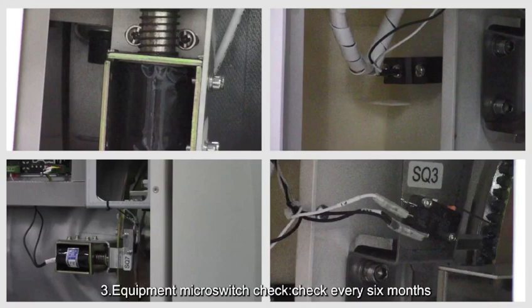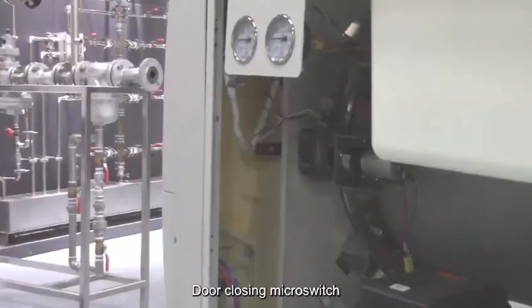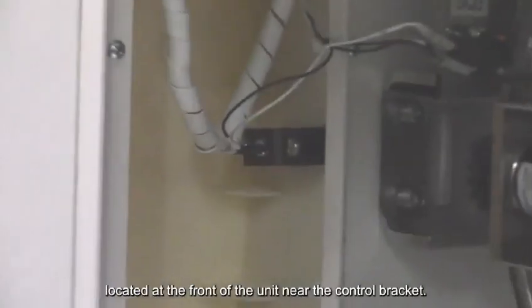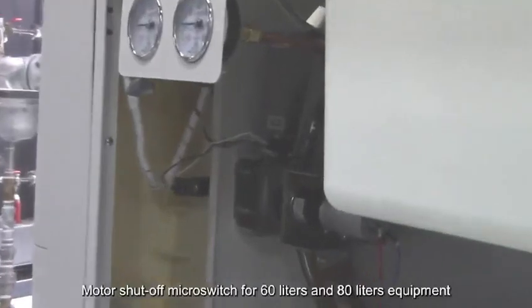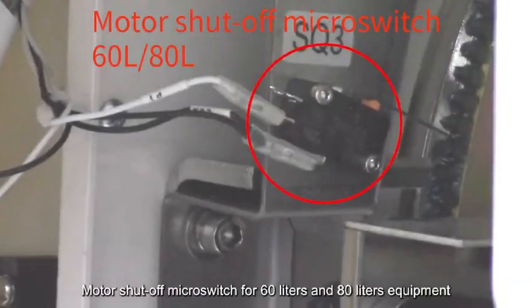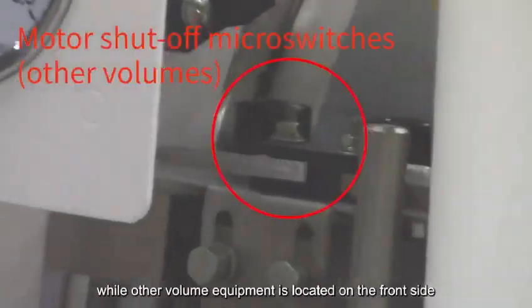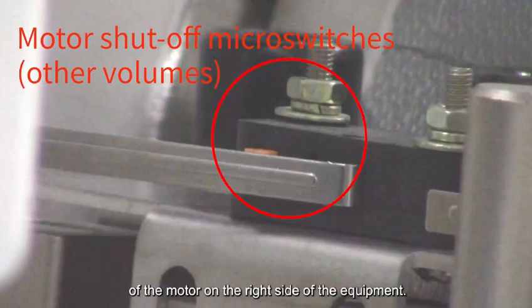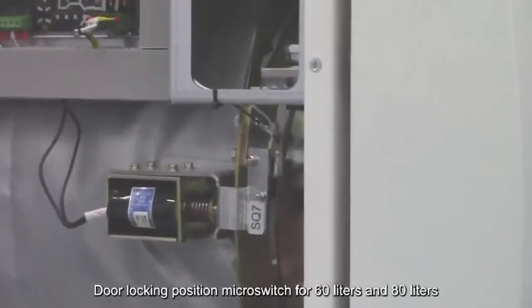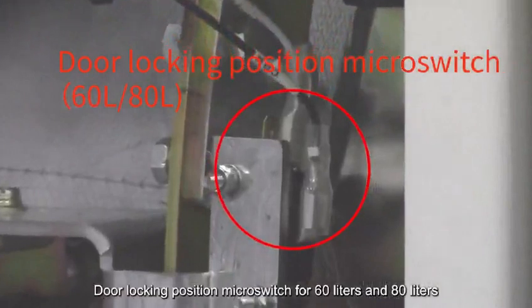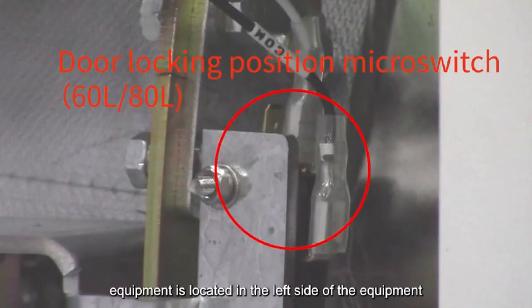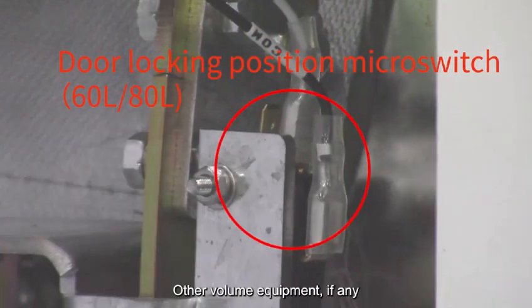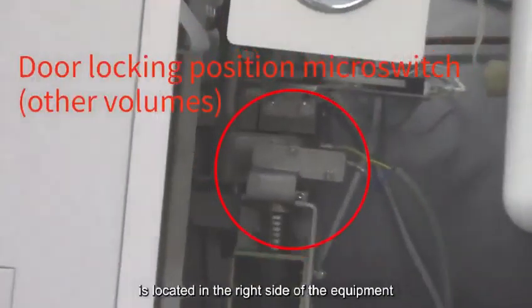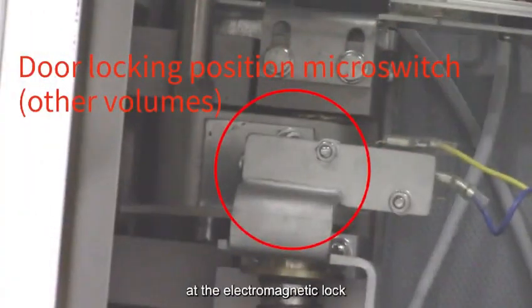3. Equipment microswitch check. Check every 6 months. Focus on the following microswitches. Door closing microswitch, located at the front of the unit near the control bracket. Motor shutoff microswitch: for 60 liters and 80 liters equipment it is located at the right end of the equipment under the door motor, while for other volume equipment it is located on the front side of the motor on the right side of the equipment. Door locking position microswitch: for 60 liters and 80 liters equipment it is located in the left side of the equipment at the electromagnetic lock. For other volume equipment, if present, it is located in the right side of the equipment at the electromagnetic lock.